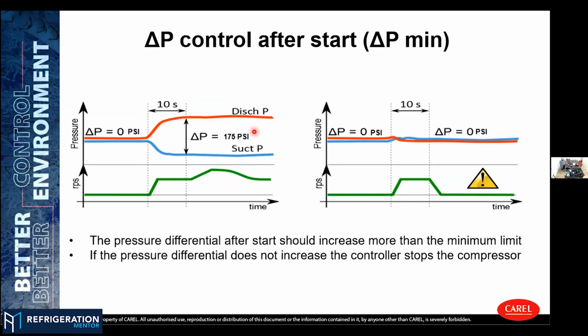Yeah, and we have some pressure control, as I mentioned. So we expect to see some pressure differential just after starting up the compressor. So we can make sure that this compressor is running in the right direction, clockwise, not anti-clockwise. These are some electronic protections that we can add when you are using BLDC technology.